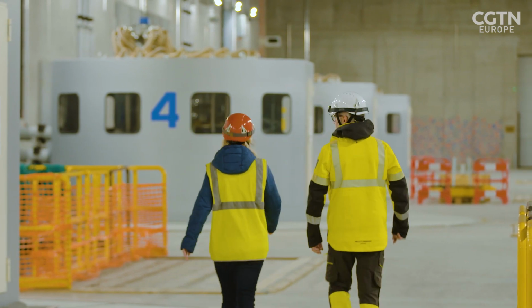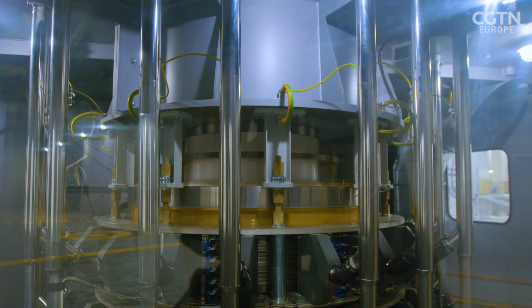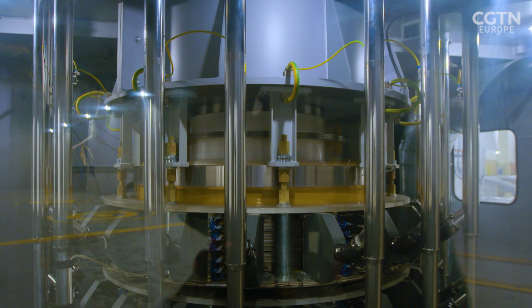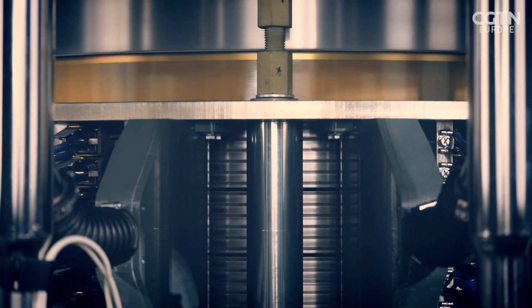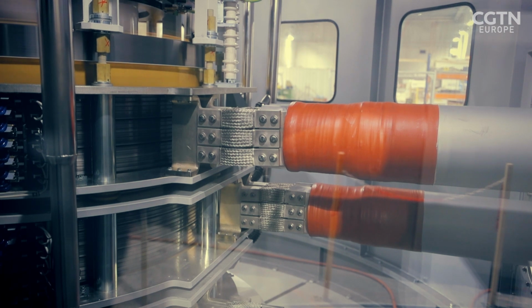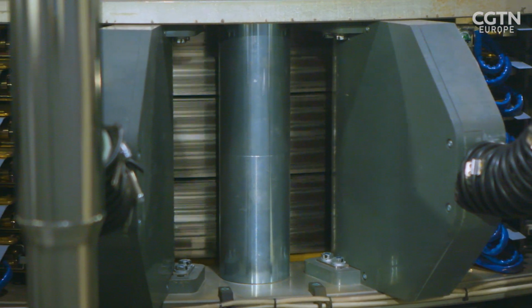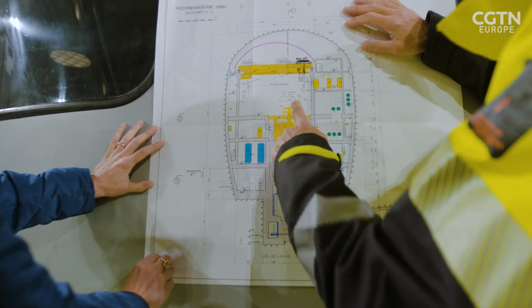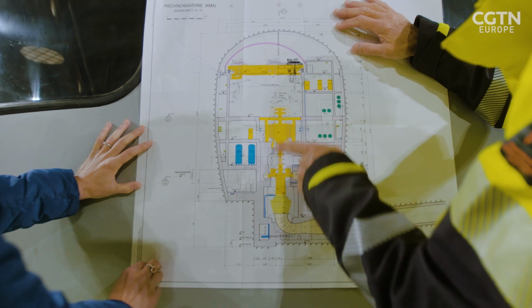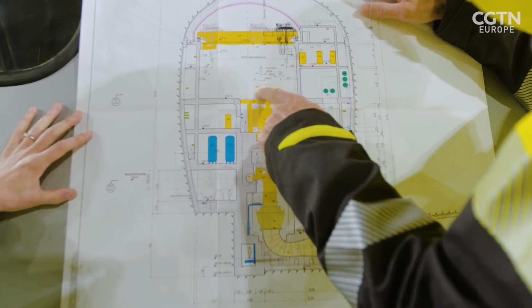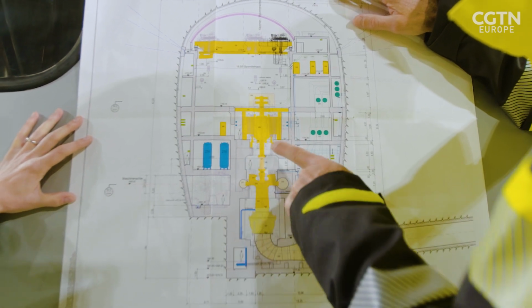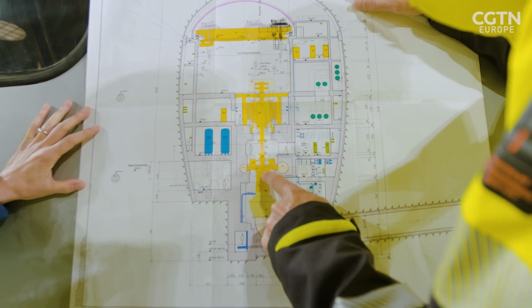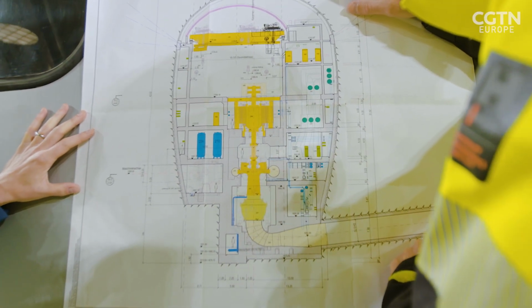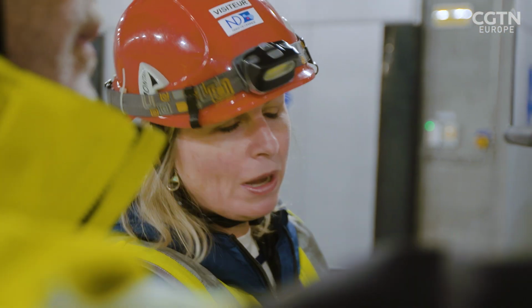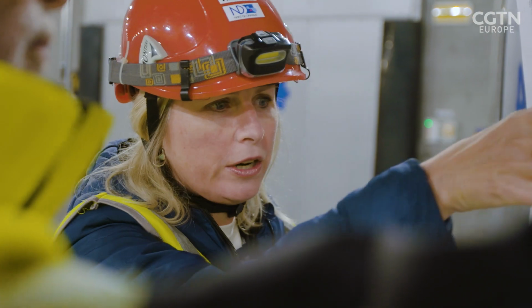Here is a place where we inject the excitation current to create the magnetic field of the rotor. All electrical generators require excitation to create electrical energy. Regulated direct current is provided to the coils that produce the magnetic field needed to excite the motor or generator. So we are just standing next to this small part of the machine. As you can see, there is a lot of machinery underneath. Here you have the excitation, the motor generator, the intermediate shaft, the turbine itself, and then the pipes connecting to the lower lake. This is just a tiny part of it. I didn't realize just how much machinery there is, 1, 2, 3 floors down.